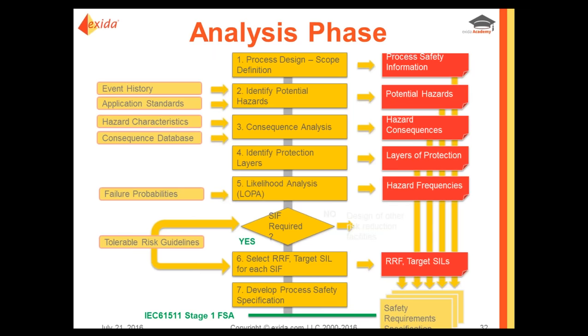In a safety instrumented system designed to automatically protect the industrial process, the steps required to do this cannot begin until the conceptual design of the product is complete. At that point, the process is examined for its potential hazards. The risk of each hazard is assessed by estimating the likelihood or frequency of occurrence and the consequence or magnitude if it does occur. For those risks that need to be reduced, a safety requirement is created.